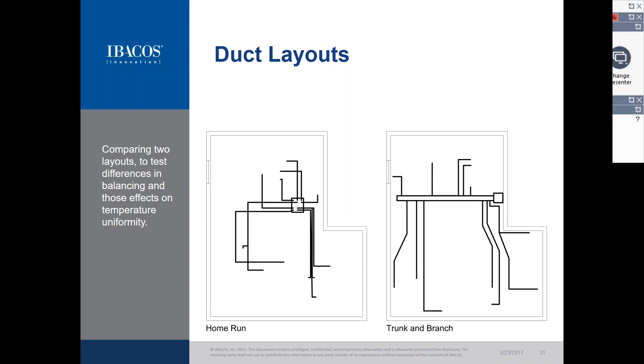The plug-and-play concept is envisioned as being more compact, radiating from a central point, while the trunk and branch layout was far more spacious. We studied the difference between these two layouts and their impact on temperature uniformity. We also used an airflow network implementation to simulate large openings such as doors and connections between zones, and simulated air infiltration to account for that through the enclosure.